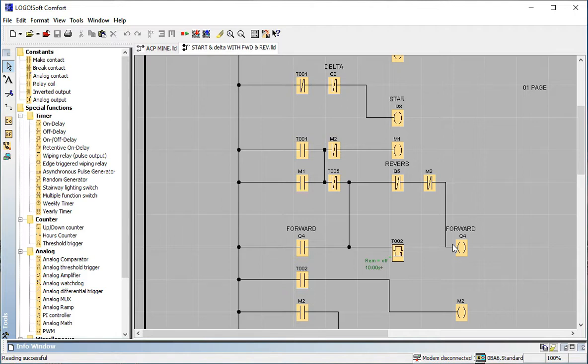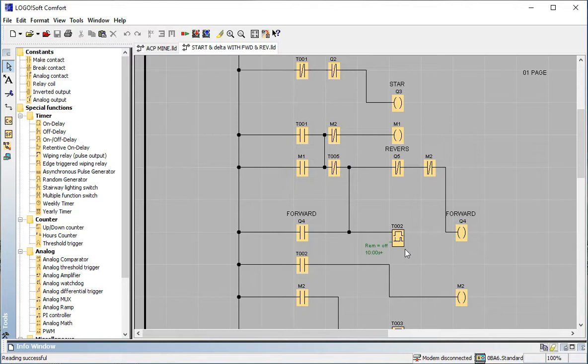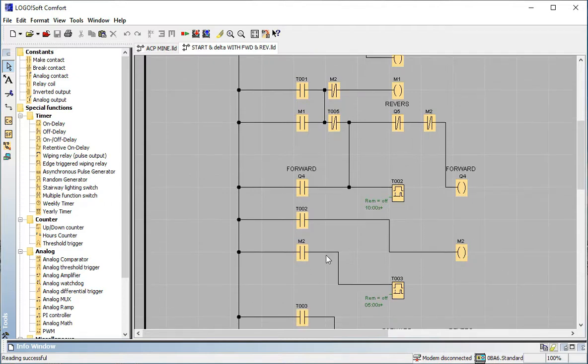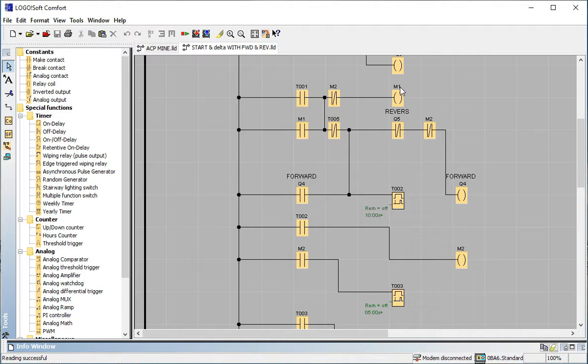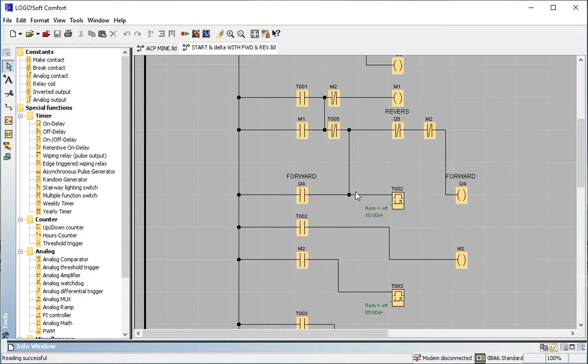Q4 NO becomes NC — when Q4 is ON, Timer 2 starts counting 10 seconds. This is your destination time, which depends on your industry requirements. After 10 seconds, Timer 2's NO becomes NC and memory M2 is connected. When this memory is connected, it turns off memory M1 — as a result, Q4 (forward) turns off. This latching lesson is important: when you need to turn off a specific output among many outputs, you must use this latching method.